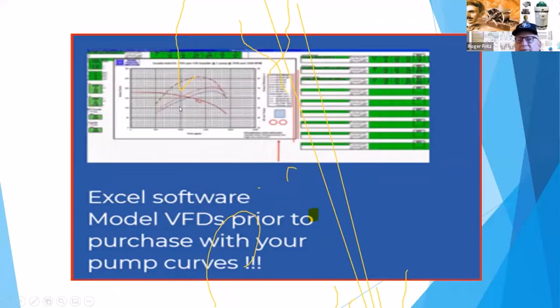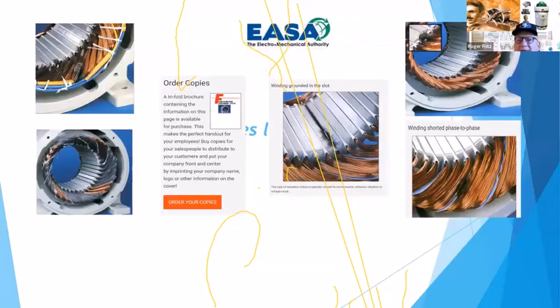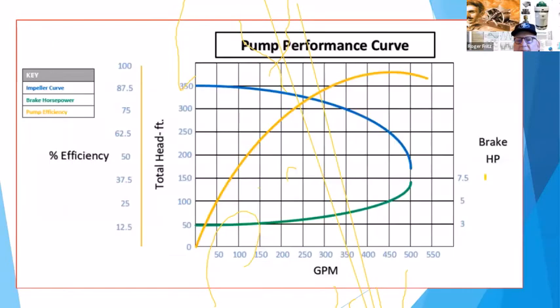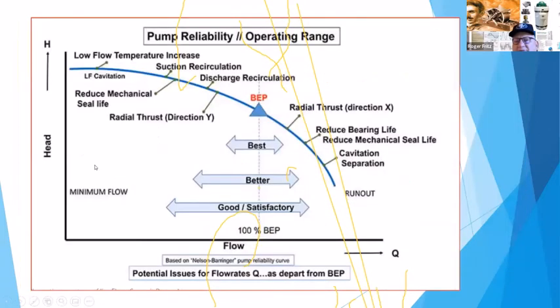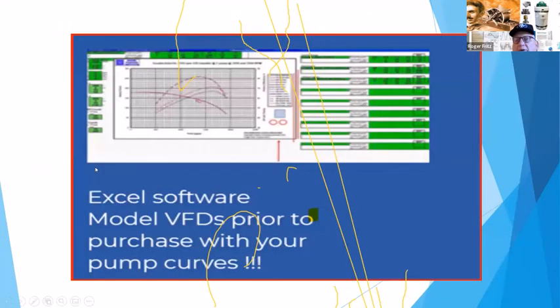So if you go adjust the speed and you haven't pre-checked, you may, by the time you slow it down over a small amount, I see a lot of people slow a VFD down even to like 55 Hertz, so instead of running at 1800 RPM, it's running at 1700 RPM. If it's too close on that pump curve to its design point, all of a sudden it goes right into cavitation and the motor starts having trouble or just totally stops pumping water.